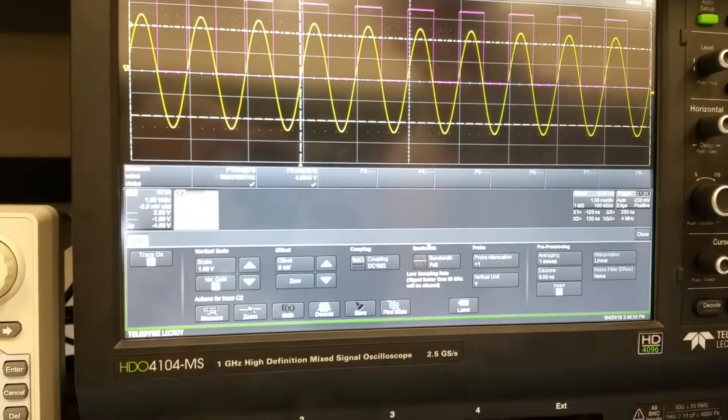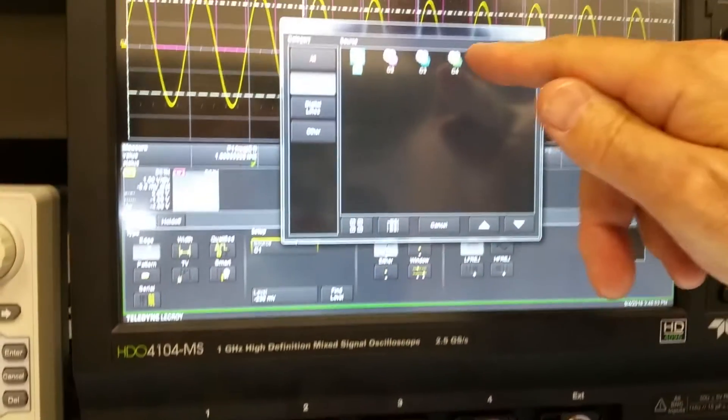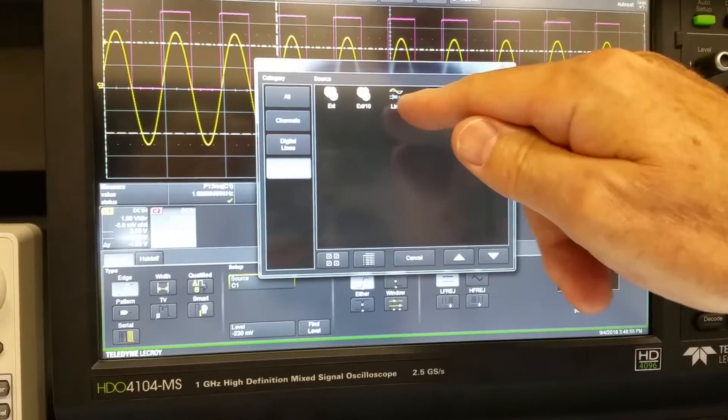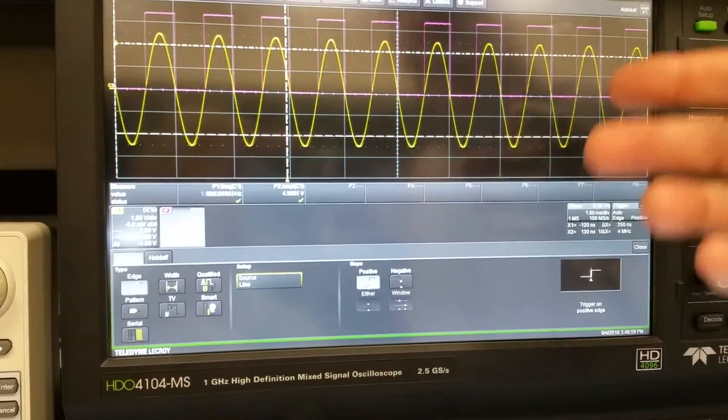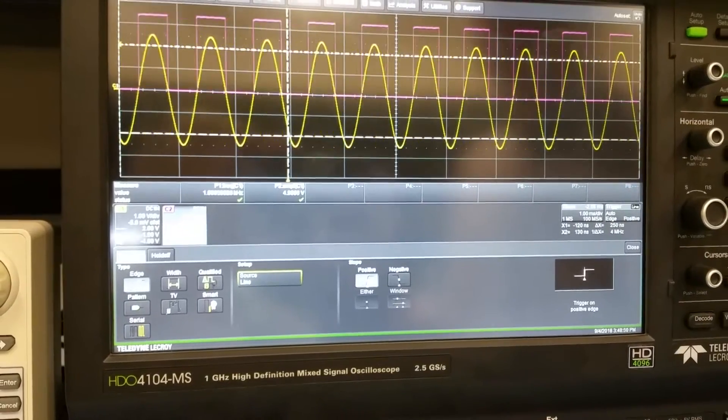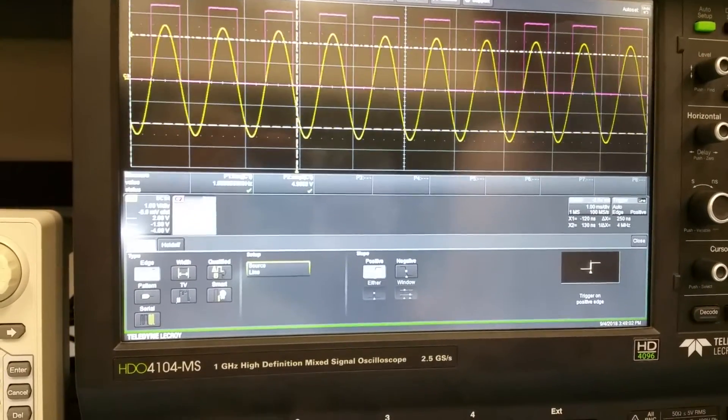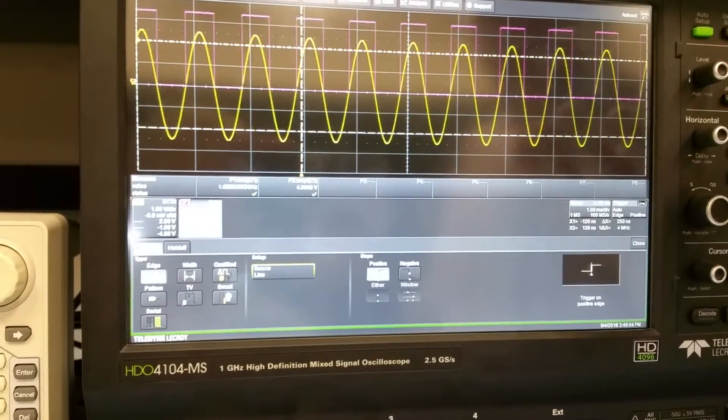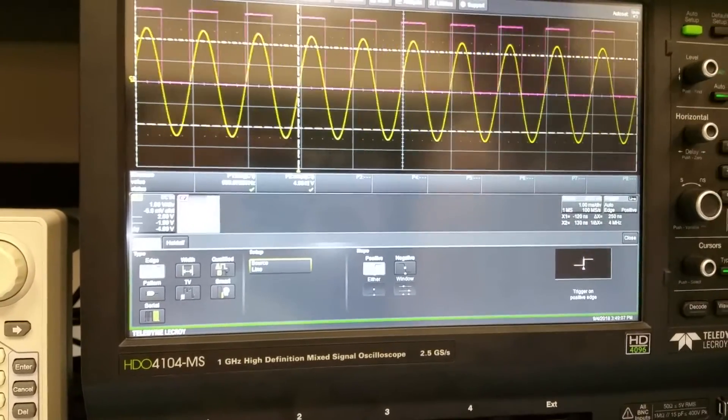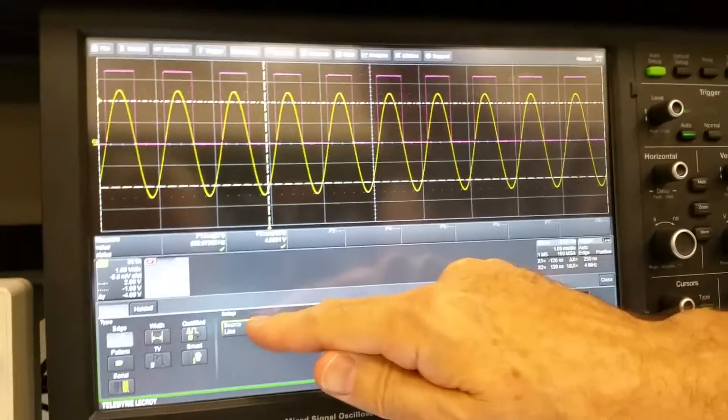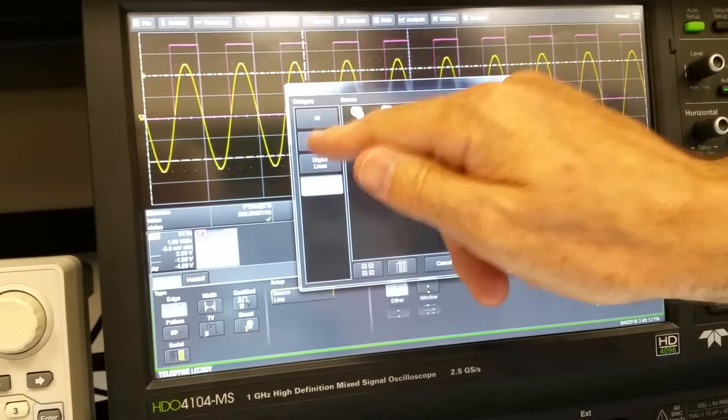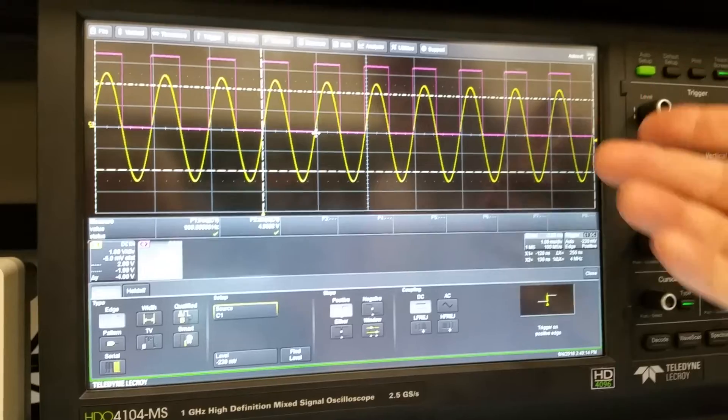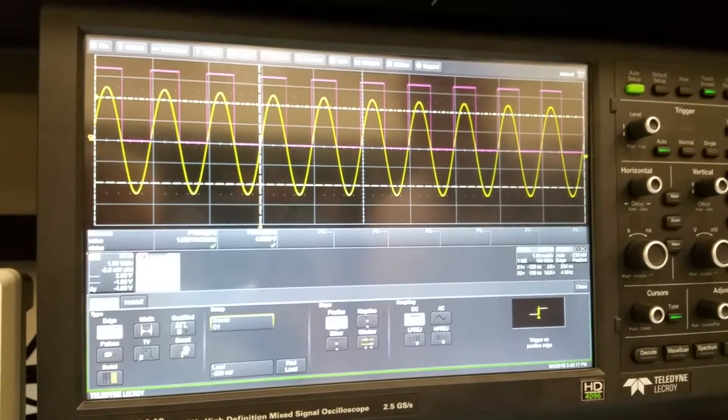And there is one more mode for triggering, and that is line triggering. So if you choose line, which may not work so well here, we'll see what happens. That means that whatever you're doing is synced to 60 hertz, the line frequency, but we're not. So it can't trigger on the line frequency because we don't have any relationship to that 60 hertz. So we go back to channel one, channel one, everything is good, and we have a nice clean signal.